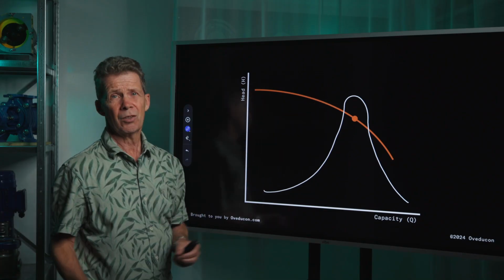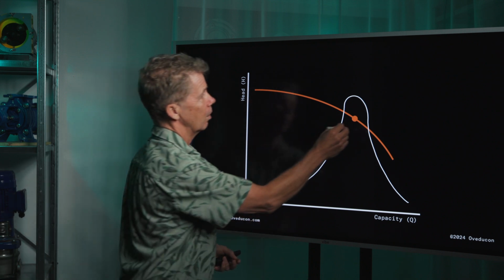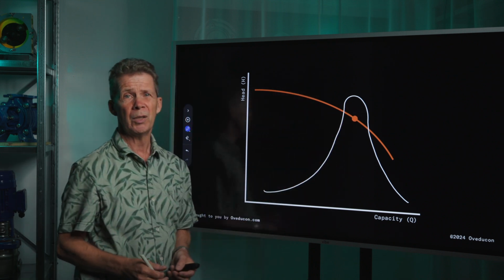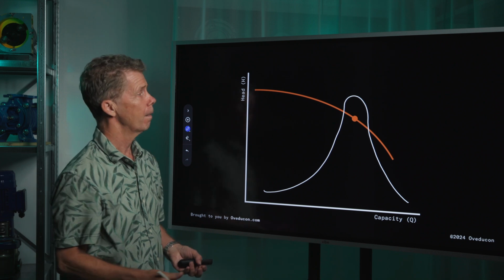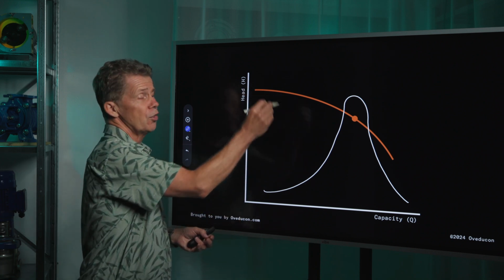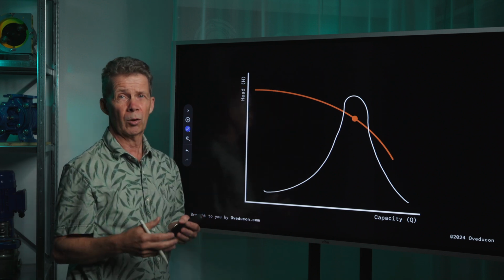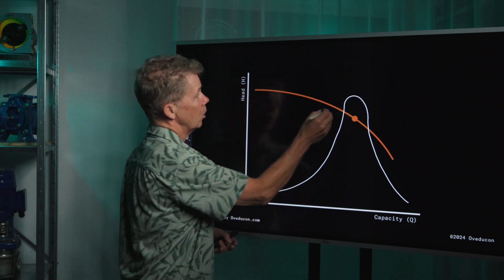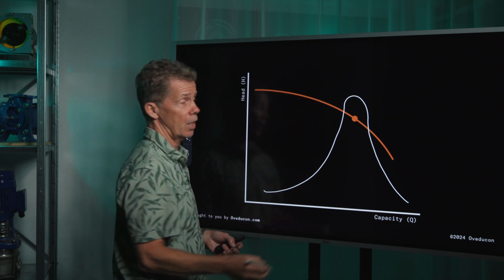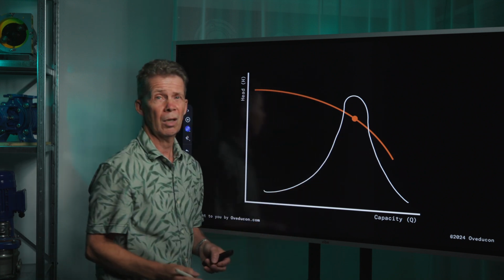You have the highest reliability on the BEP of your pump. And there are different failure modes on the curve according to Barringer-Nelson. You have 6 on this side and you have 2 on this side. And every point on that curve is a different failure mode.